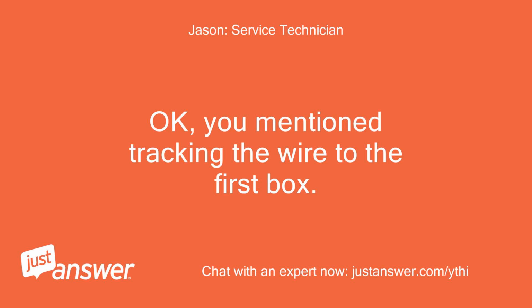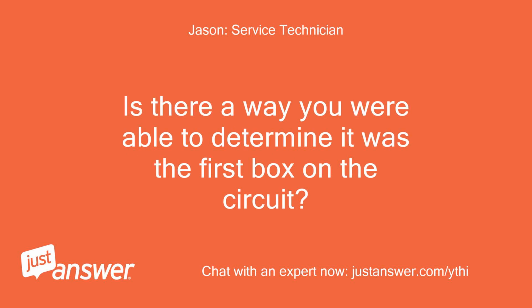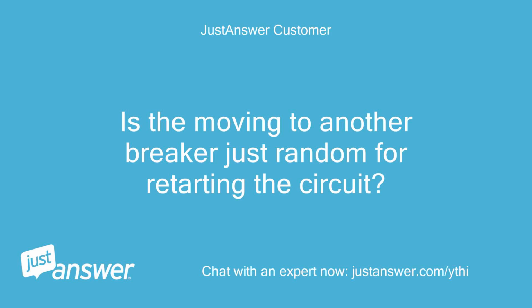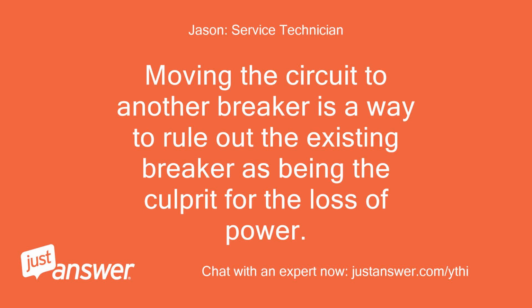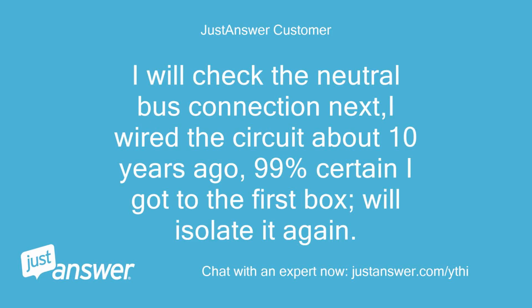Okay, you mentioned tracking the wire to the first box. Is there a way you were able to determine it was the first box on the circuit? Is moving to another breaker just random for retesting the circuit? Moving the circuit to another breaker is a way to rule out the existing breaker as being the culprit for the loss of power. I will check the neutral bus connection next. I wired the circuit about 10 years ago, and I'm 99% certain I got to the first box. We'll isolate it again.